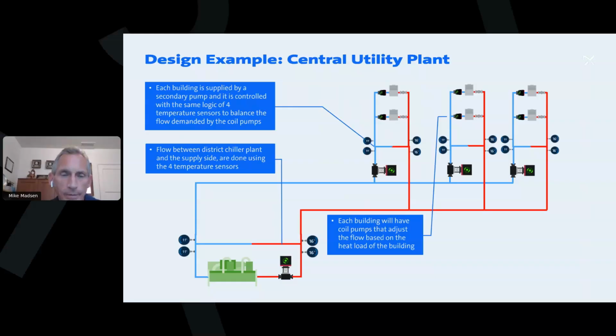Yes, and that one we got. I am seeing some ones. Do we still need the BMS to control for the temperature reset? Great question. So yes, we're doing local control on the smart pumps, the Magna 3s, but then you often want to do temperature reset. Some items in the Magna 3 are rewritable, and set point is one of those. So you just send the pump a signal from the BMS for what you want the new set point to be, and it will automatically switch over to that.